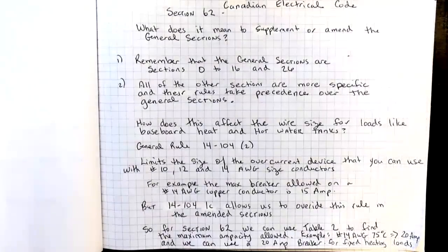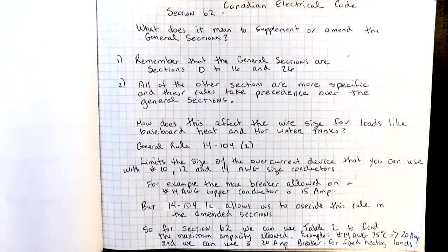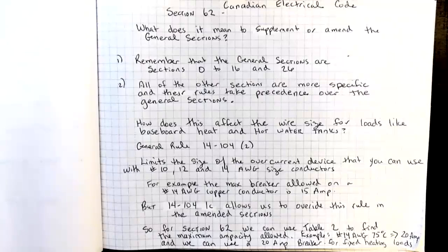I just want to remind you about the supplementary or amended sections of the code versus the general sections. When we talk about section 62, it is a supplementary section. The general sections in the Canadian Electrical Code are sections 0 to 16 and 26. They are more general — not specific. All the other sections are more specific, and their rules actually take precedence over the general sections.